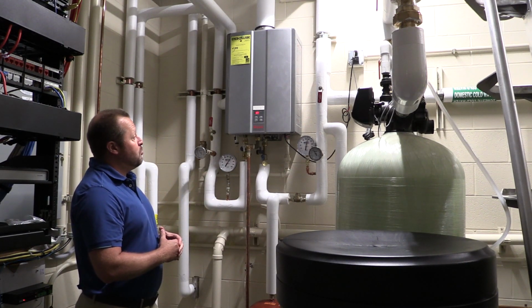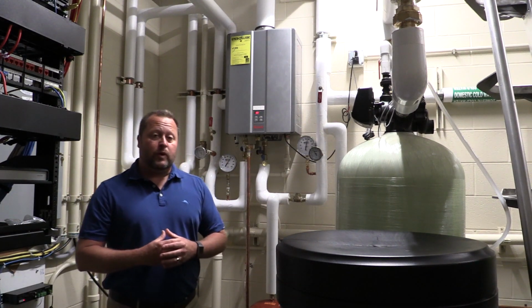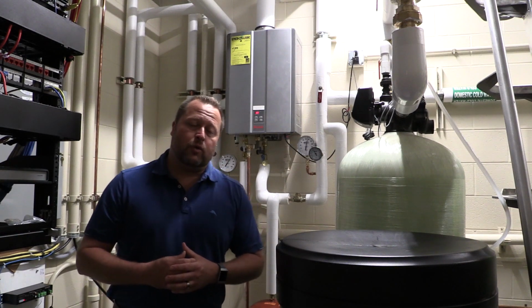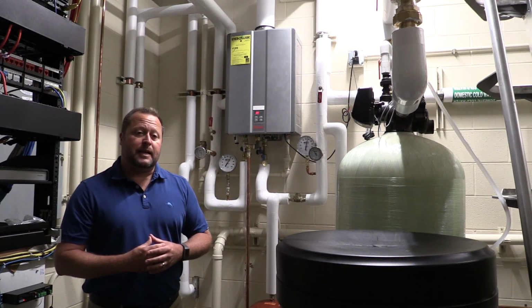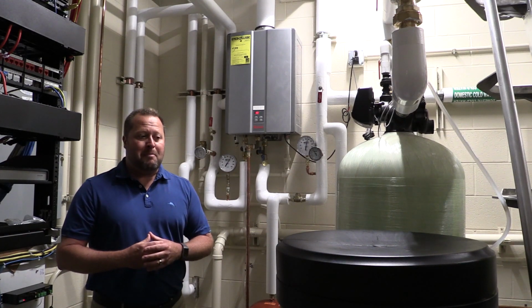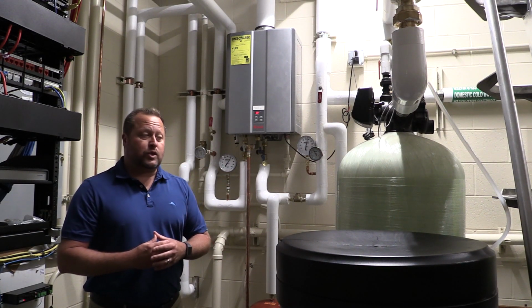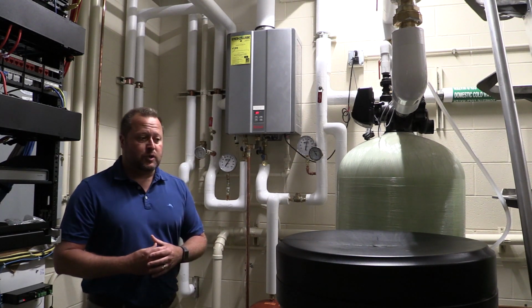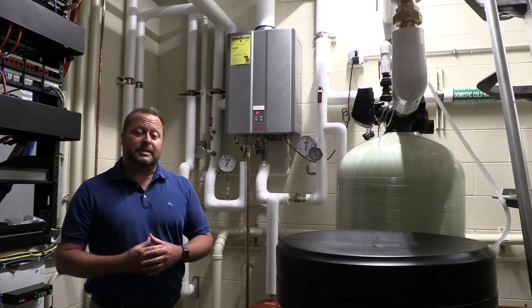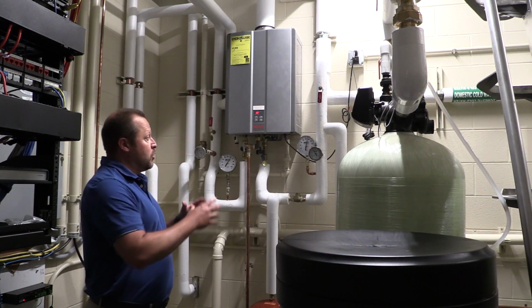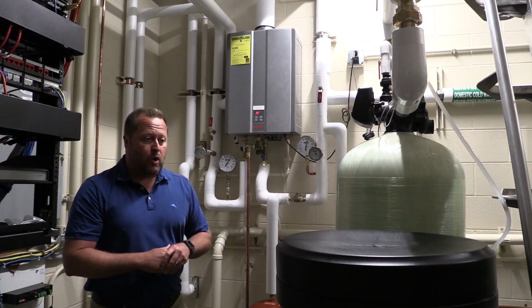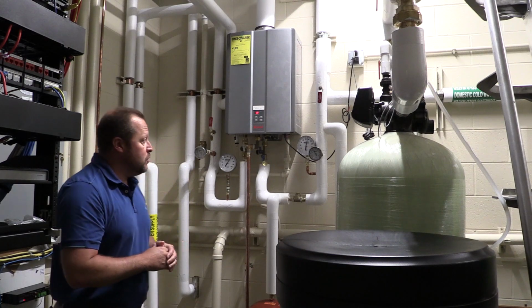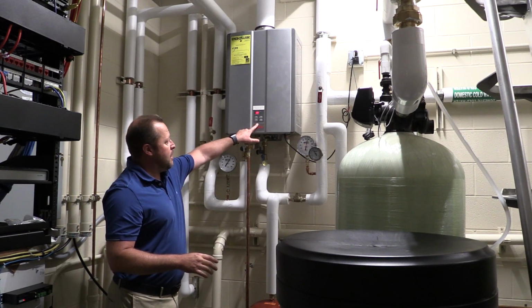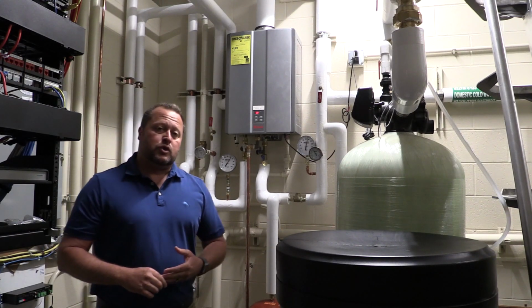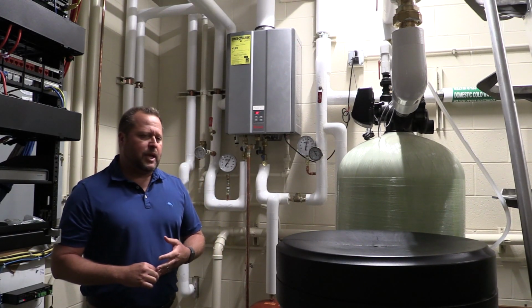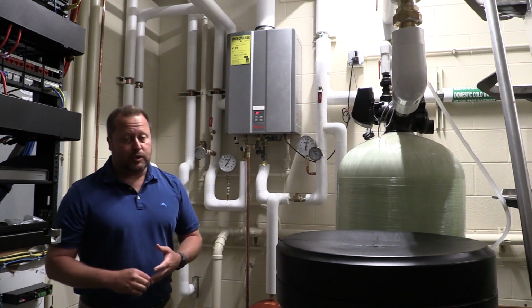The other thing is, all the components on the inside of this unit are easily removed. Rinnai has redesigned the unit so it is more efficient, and at the same time you can get the heat exchanger out and back in roughly in 30 minutes. So worst case scenario, you lose a heat exchanger, have a leaking heat exchanger, you should only be down for about 30 minutes to get it taken out and put back in. So all the other components are modular on the inside. There is no longer any push button or dip switches on this unit. All the settings are done on the keypad, which is done by the installing contractor. So 14 parameters in a commercial application. This is a residential, so there's 12 parameters in here that you can change.